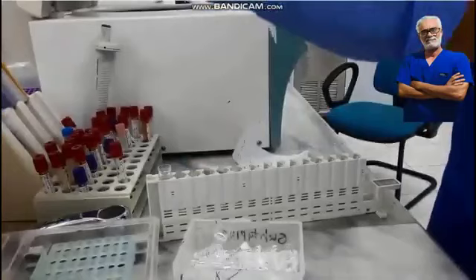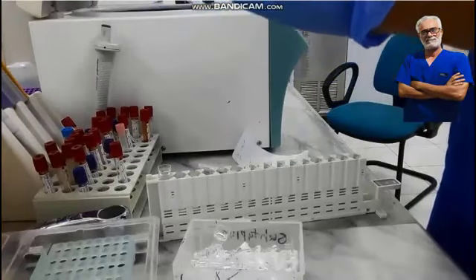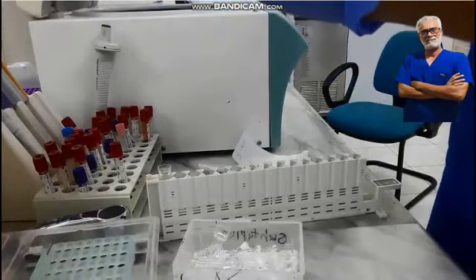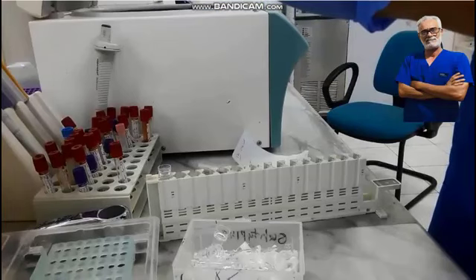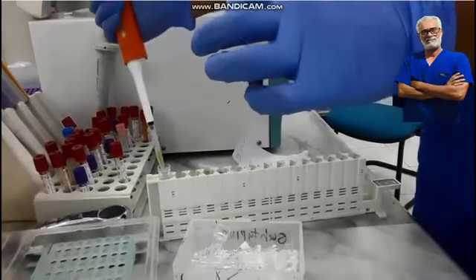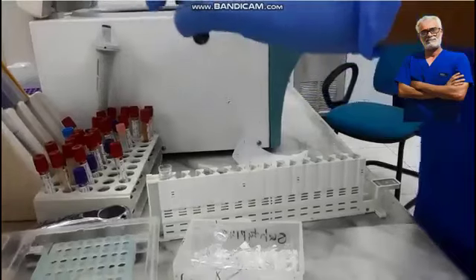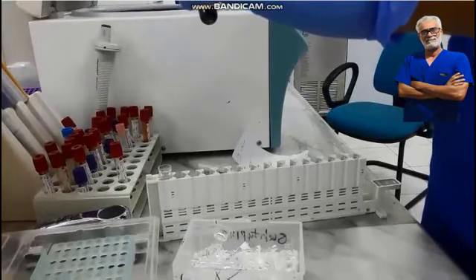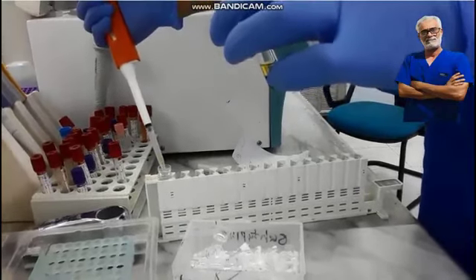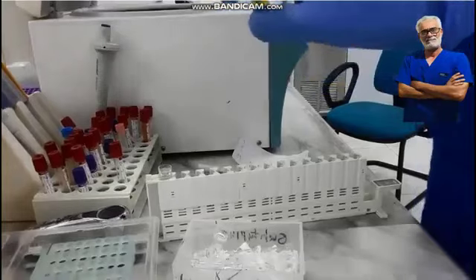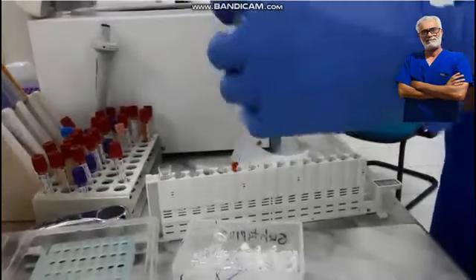Why are we so focused on this? Because it ensures that the high-precision robotic probe can easily reach the liquid surface and aspirate the required amount accurately without sucking in any air bubbles or touching the bottom of the cup. This simple step is what prevents many common technical errors and ensures the integrity of your medical reports.